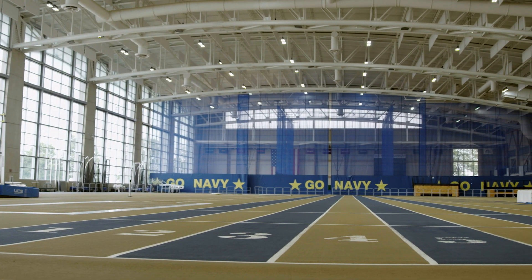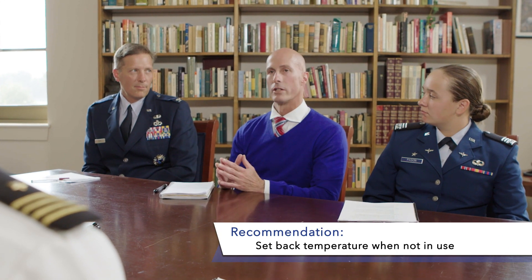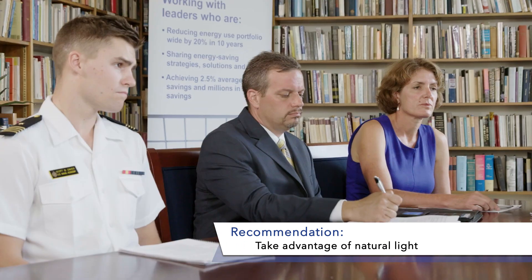I appreciate you taking a look at it because I really value your suggestions. I was thoroughly impressed with the renovations at the Wesley Brown Fieldhouse. There were a couple of things to mention though — we went in there and there was one person in the track area and the temperature was sub-70 degrees. There may be some opportunities to set back your temperature when it's not in use. And your LED lights, I loved them. But with the daylighting coming in through the window wall system, maybe we can step those back — either reduce illumination or shut off banks of lights toward the window, since you don't need that illumination there.